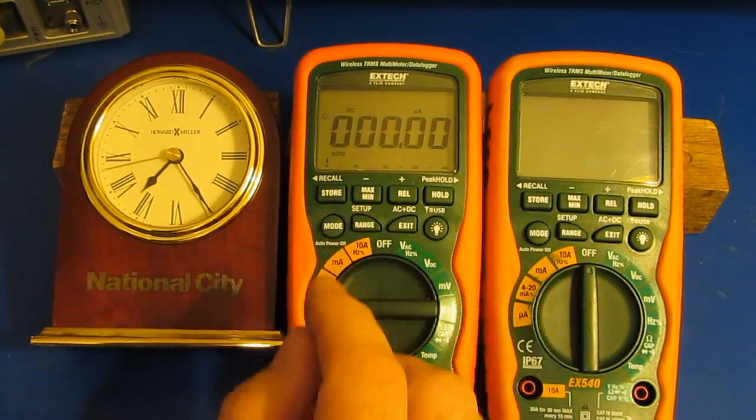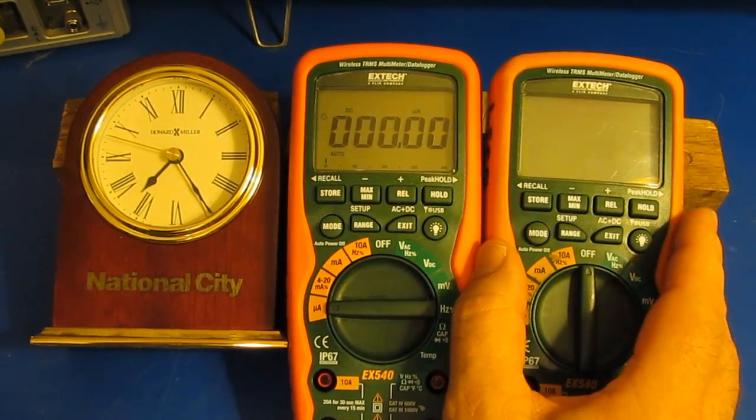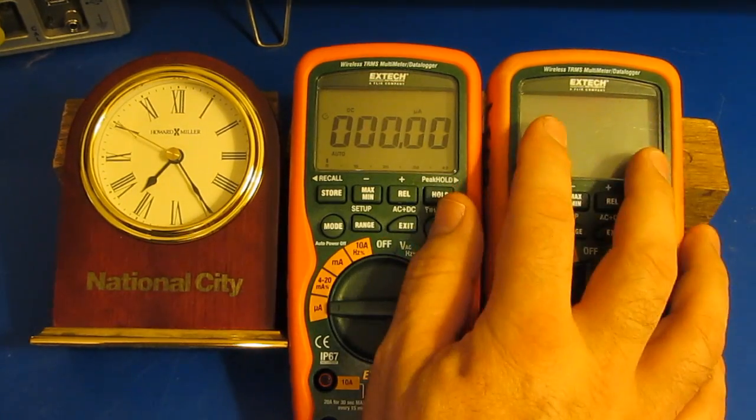As I started to disassemble this meter and do the repairs, as I removed the back cover, one of the things I noticed was there was no shield on the back cover. So I dismantled the original meter and sure enough it had the shield.